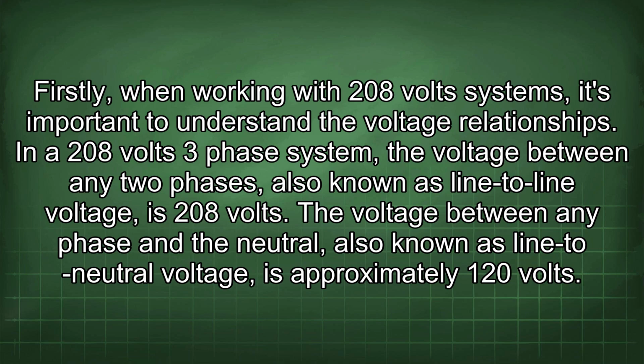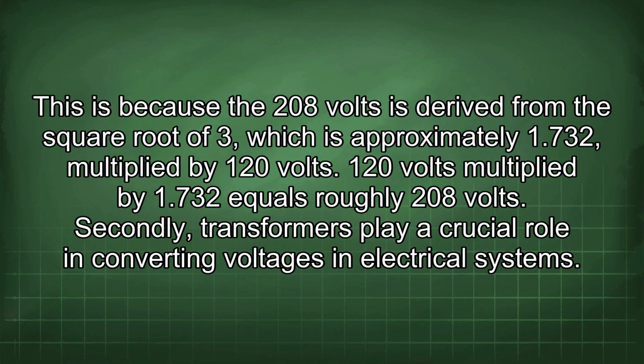In a 208 volts three-phase system, the voltage between any two phases, also known as line-to-line voltage, is 208 volts. The voltage between any phase and the neutral, also known as line-to-neutral voltage, is approximately 120 volts. This is because the 208 volts is derived from the square root of 3, which is approximately 1.732, multiplied by 120 volts. 120 volts multiplied by 1.732 equals roughly 208 volts.